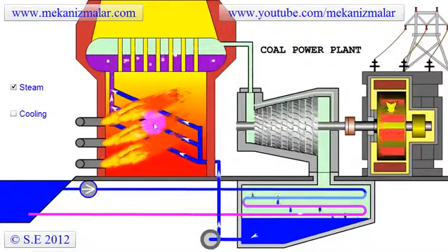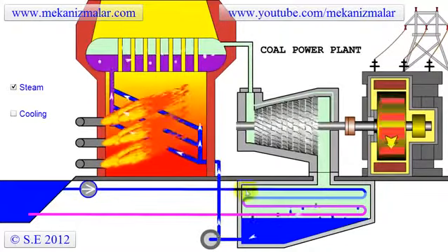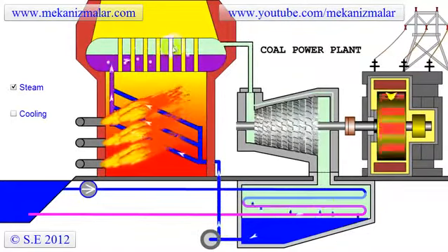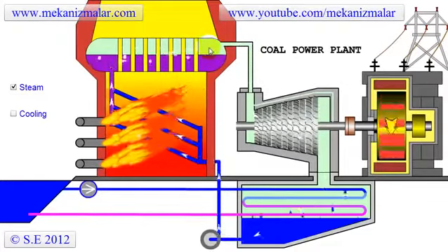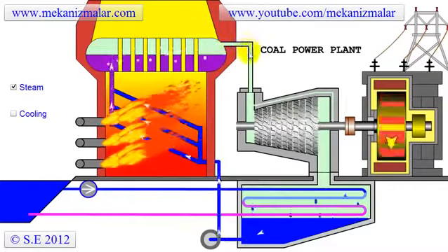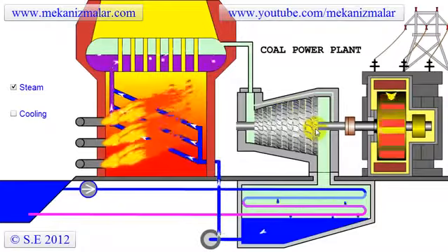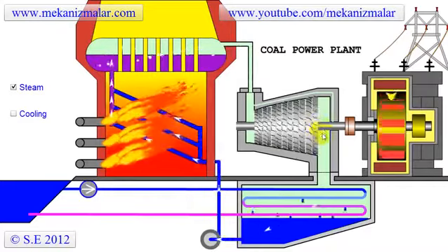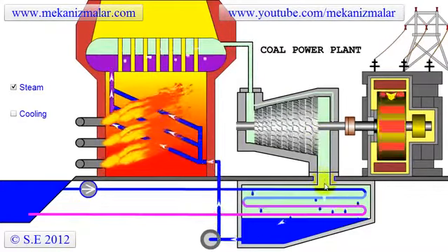First, intense heat inside the furnace heats the water within the coils, which is coming from the condenser. This heated water is forced to the boiler where it evaporates. The pressure inside the boiler can be more than 200 bars. The high-pressure steam obtained in the boiler is sent to the steam turbine, which passes the steam between fixed and rotating sections, converting the energy stored in the steam to mechanical energy. The steam leaves the turbine at close to vacuum pressure, near condensation temperature.